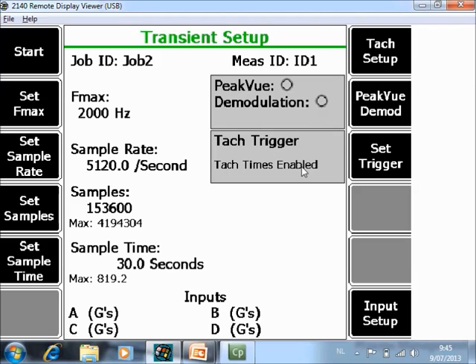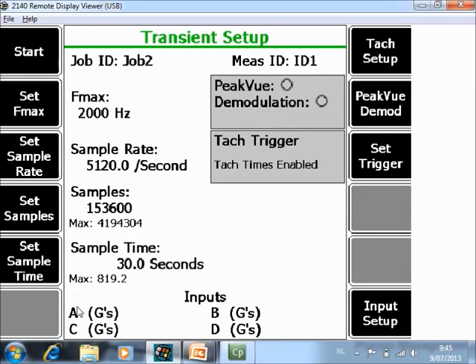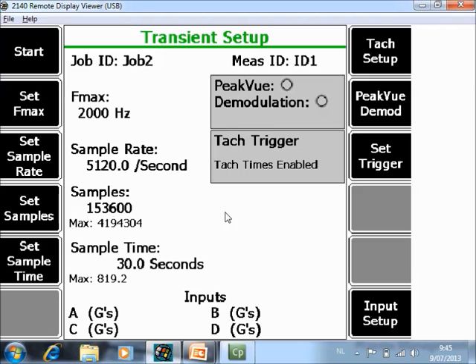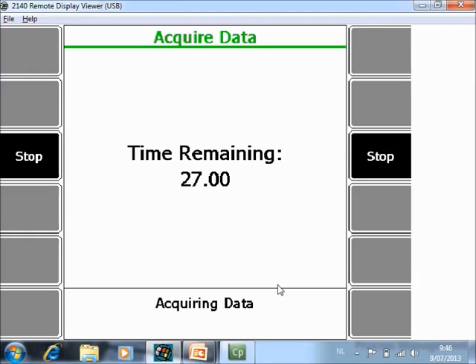For the tach, I specify that I want to work with the tach trigger on. That means that data collection will only start when a tach pulse is coming in, and I also want to store the tach pulses. For my input, I have my 4 sensors. When I now press start to collect data, he will measure the raw signal for 30 seconds. In these 30 seconds I will start up a machine and I will run out a machine. The machine will go twice through its natural frequencies.